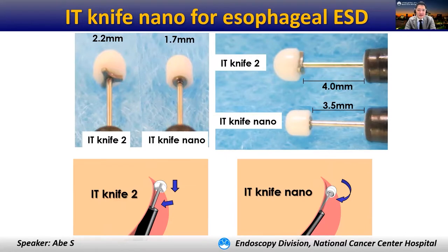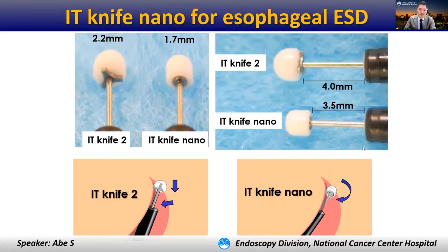In terms of ESD device, the IT knife nano is specially designed for esophageal and colorectal ESD. The IT knife nano has a smaller insulative ceramic tip and a shorter blade compared with the IT knife 2, which is mainly used for gastric ESD. The IT knife nano facilitates entering the submucosal space, and its backside electrode is small and disc-shaped, which minimizes injury to the muscle layer, allowing us to reduce the risk of perforation.